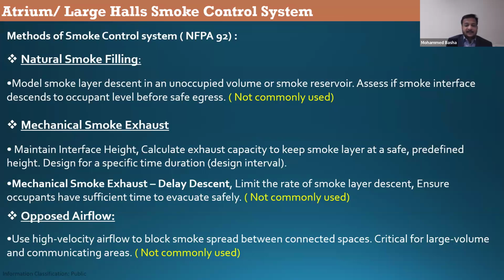Mechanical smoke exhaust. This is the common system we will be using, which will have the extract fans at the high level to extract the smoke out of the space to maintain the interface height. It must be calculated based on the smoke layer height you need to maintain at a predefined height and designed for a specific time duration.